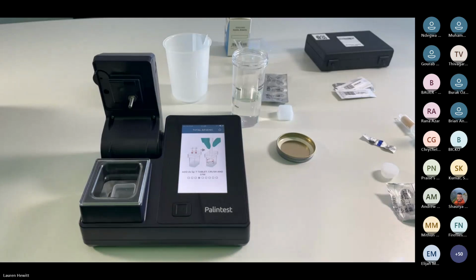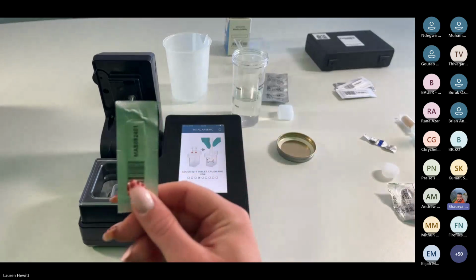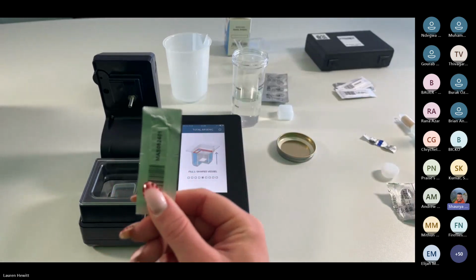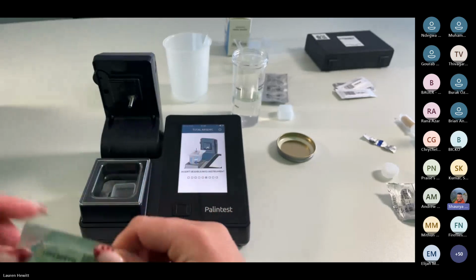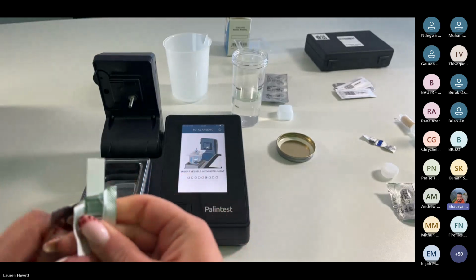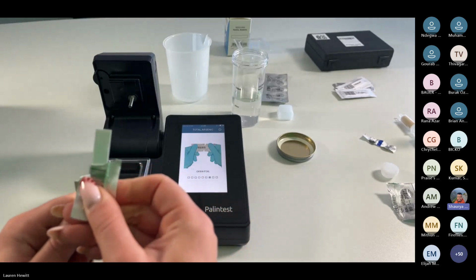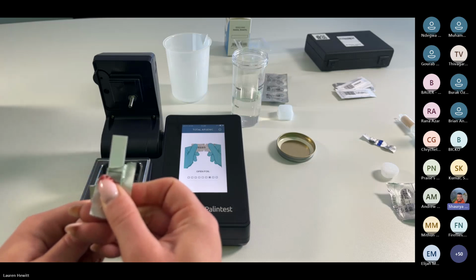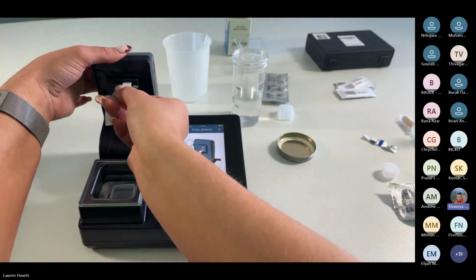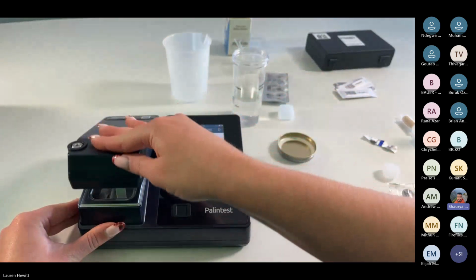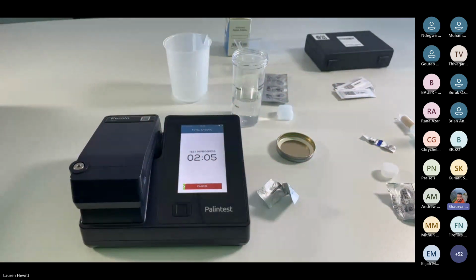Now for inserting the sensor. The best way to insert this is the barcode is on the bottom and the number is on the top. Now you want to tear off the top half of the foil so that you have the white side facing you as inserted. So you want the white side facing up, inserted into the Chemio. As far as it will go, there is a good push in there to know that it's fully secure. And then you simply close the arm and the test begins. As this test completes, in 2 minutes, you will have a result for total arsenic.